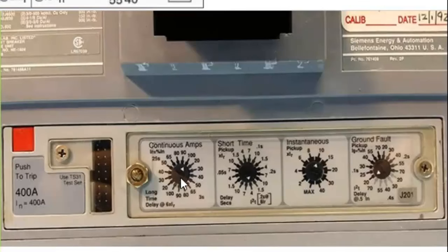So this is the continuous amp rating, as we discussed before, for you to set the nominal, that is the operating current of a circuit breaker, or to change the nominal current of the circuit breaker or the rated current of the circuit breaker. This is the short time pickup, instantaneous pickup, and the ground fault pickup.